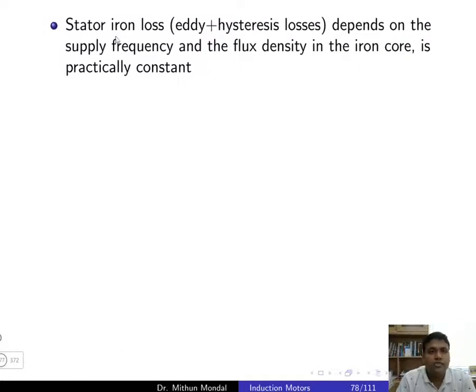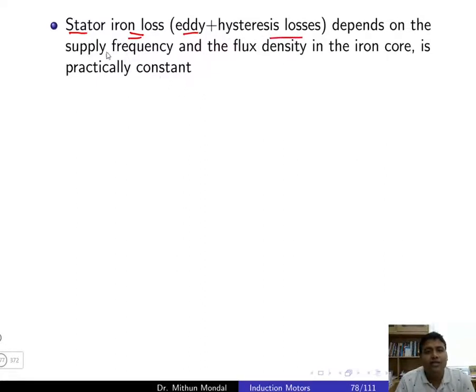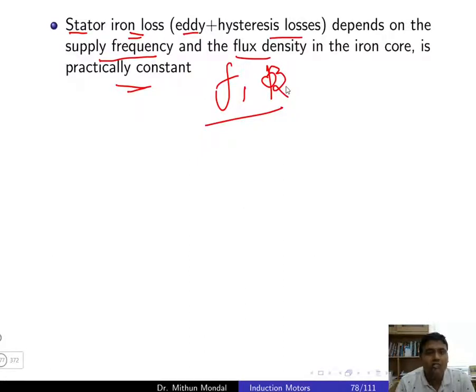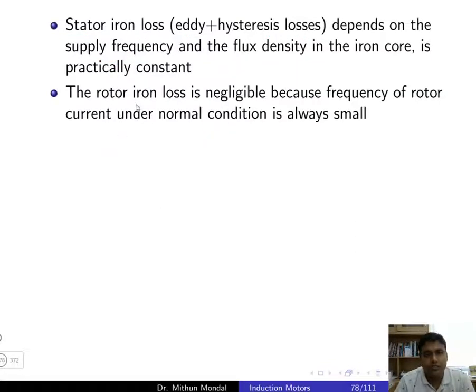In the stator, the iron loss comprises eddy current loss and hysteresis loss. These depend on supply frequency and flux density in the iron core, which are practically constant. Since frequency and flux are constant, flux density is constant, so iron loss is constant. The rotor iron loss is negligible.